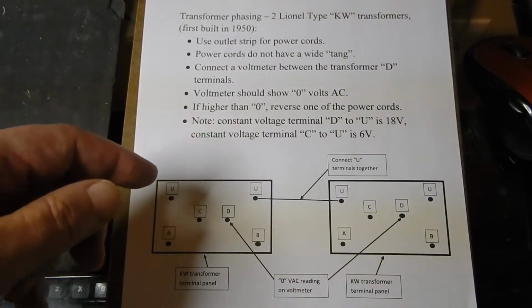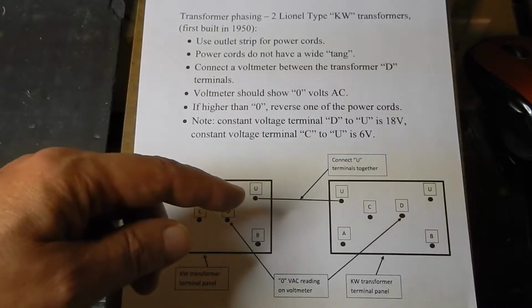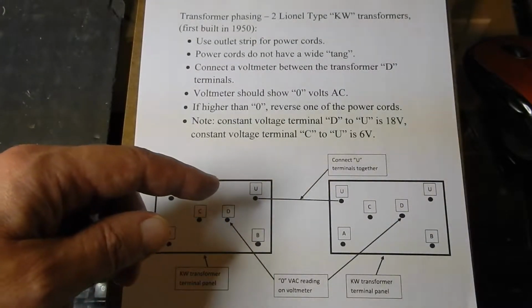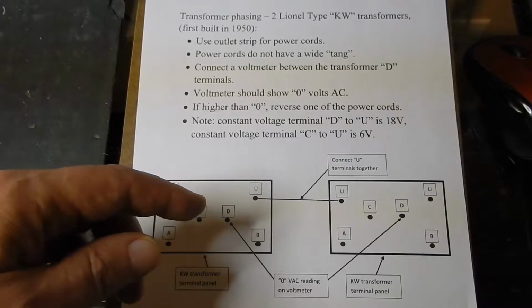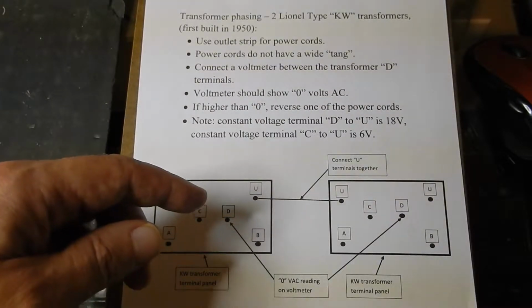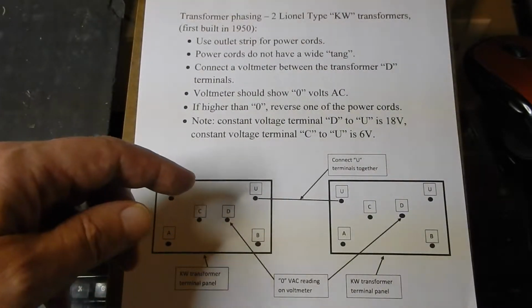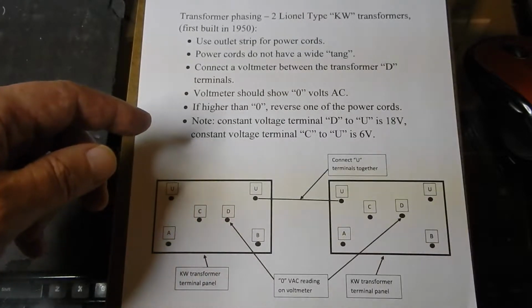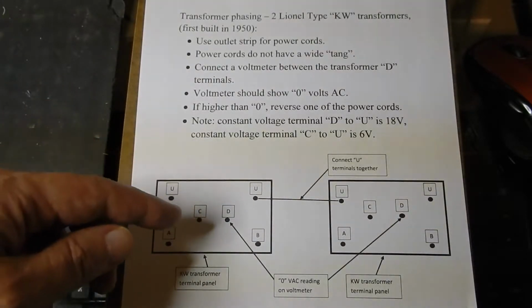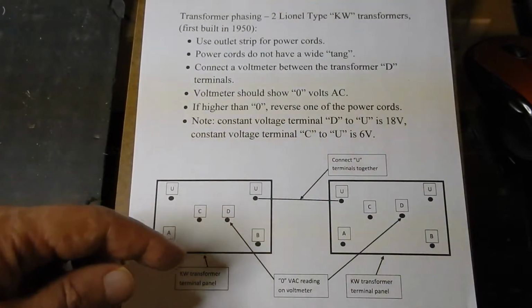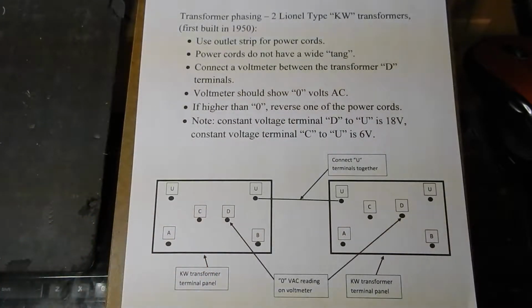What you want to do is connect the U terminals together on the 2 transformers. Plug them in, connect the U terminals together. Then connect the voltmeter between the D output on each transformer. This should read 0 volts AC. If it's higher than 0, reverse one of the power cords, and that should do it.